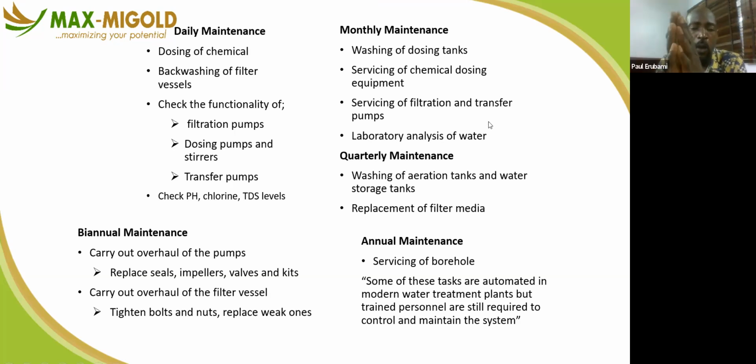If you are working as a facility manager in a water industry where you sell the water for public consumption, you need to do analysis on a monthly basis. But if you are only using the water in your facility for all the necessary domestic use, your analysis should be done once in 6 months.